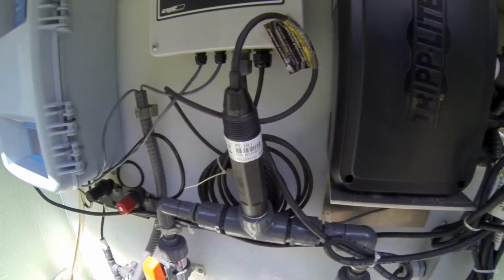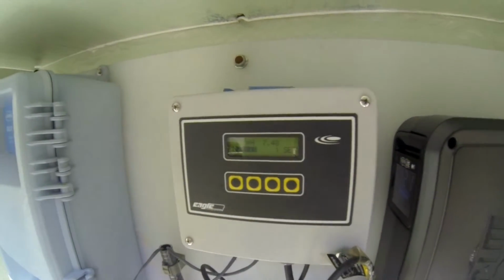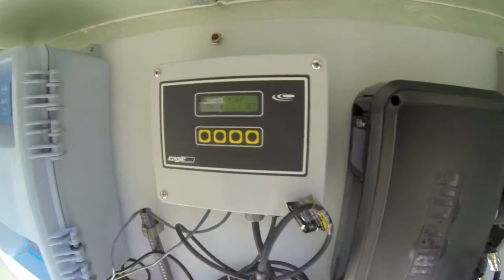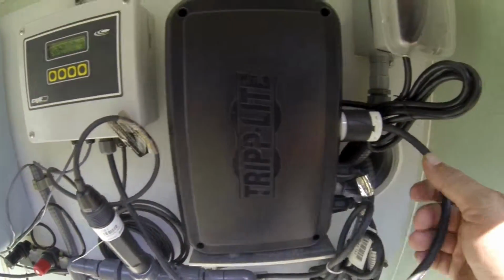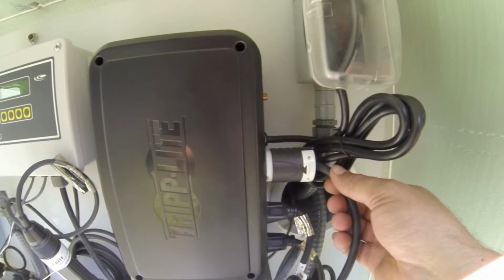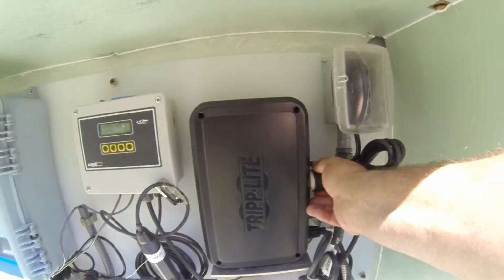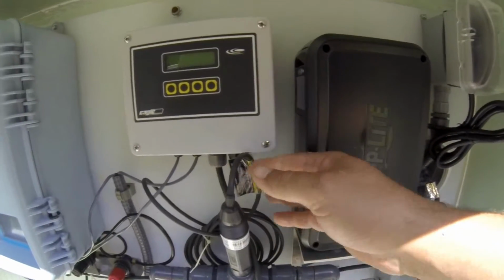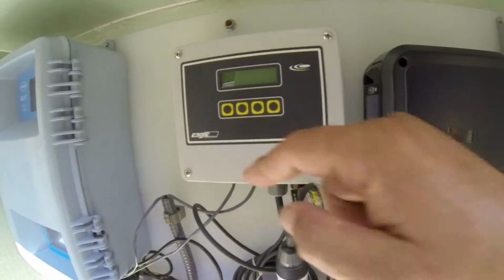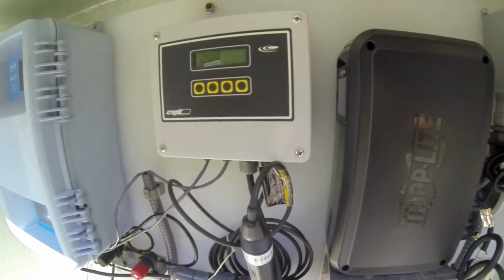So here we see the pH probe as well as the pH analyzer or display. You'll note that this is plugged into a battery backup, so at this time we're going to unplug that from the battery backup. Once that's complete, the next step is to remove these 4 screws with a Phillips screwdriver. We're going to do that now.